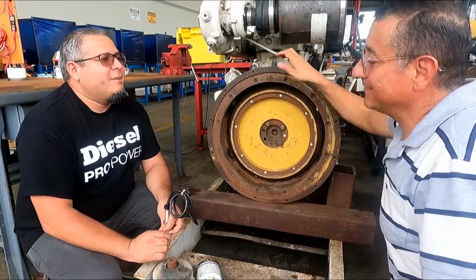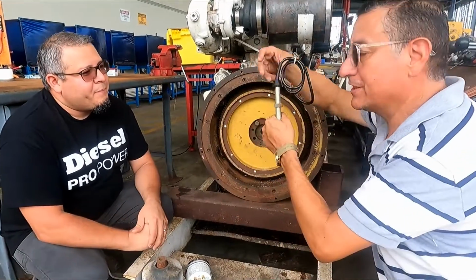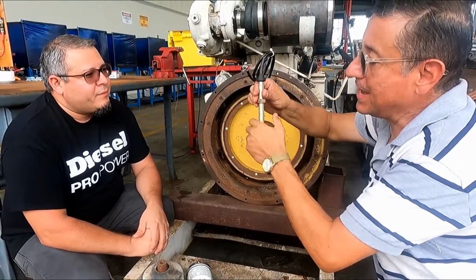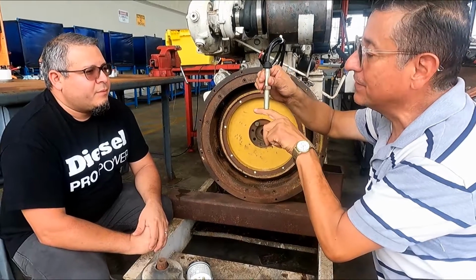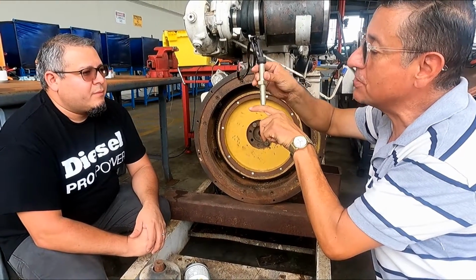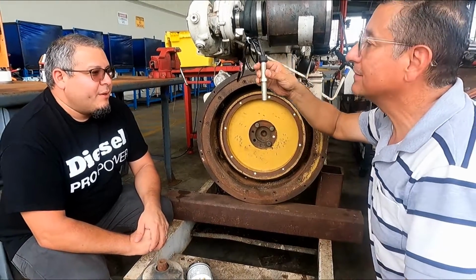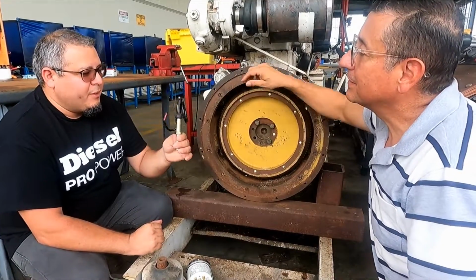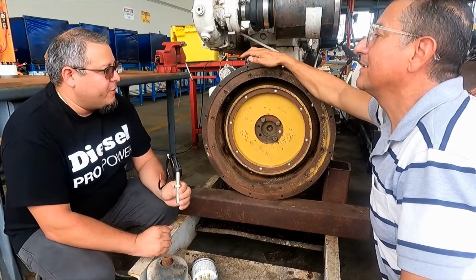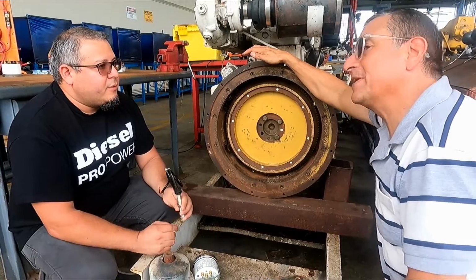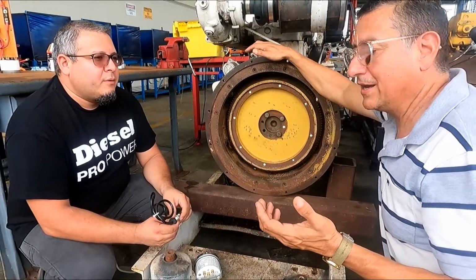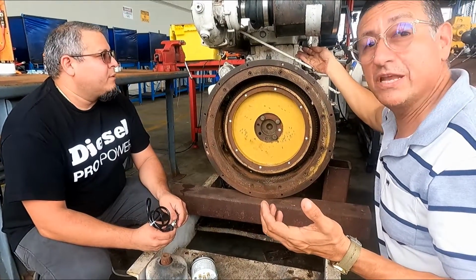Recommended, yes. You thread it in until you touch the flywheel, and immediately when you touch it, you return half a turn — that gives enough clearance for the magnetic pickup to read the signal from the flywheel. This is great, because in some cases, for example, this engine was in a generator.